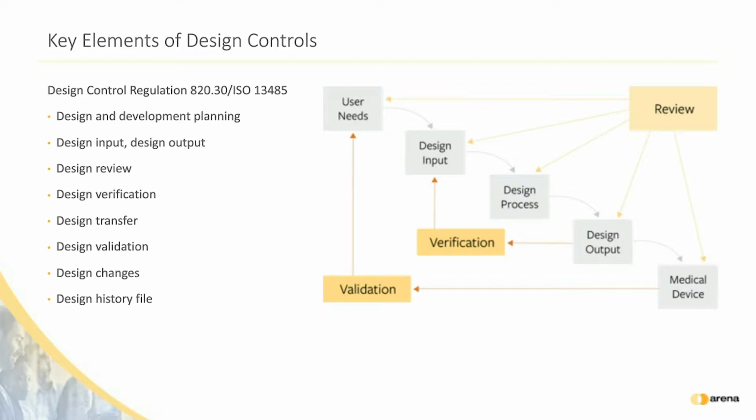Design changes are the second most cited issue under design controls. After that first revision, updating ERP and other downstream systems can become tricky. What has changed? What parts were added or removed? Is all the supporting documentation updated? You can run into trouble here. And change processes can have many variables. So we've seen people stumble over documenting this process and then following it.